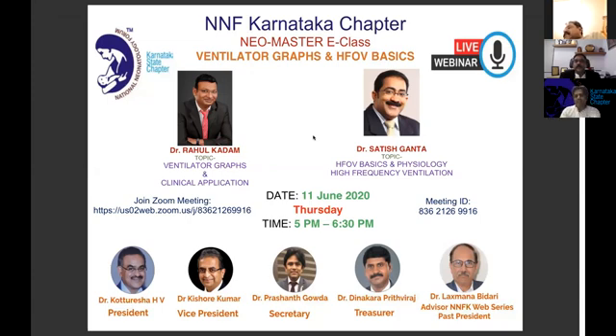How to synchronize in SIMV? I heard it synchronizes only inspiration. What about expiration? No, see, synchronized mandatory ventilation means you are setting the rate here. So try to understand the difference between SIPPV and SIMV. In SIPPV, if the baby is breathing 60 times, even if you set a backup rate of 40, if the baby wants 60 breaths, the ventilator will give 60 breaths, and each of the 60 breaths will be synchronized. That is the importance of the trigger sensitivity. Now, when the baby is on SIMV, suppose you keep a backup rate of 40 breaths, the ventilator will give only 40 synchronized breaths. The remaining, even if the baby is breathing 60 or 70 times, another 30 to 40 breaths may not be synchronized.